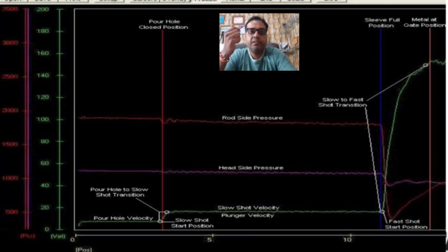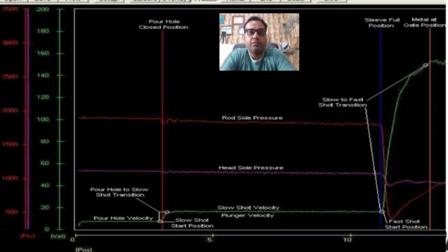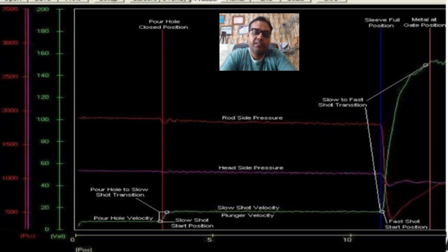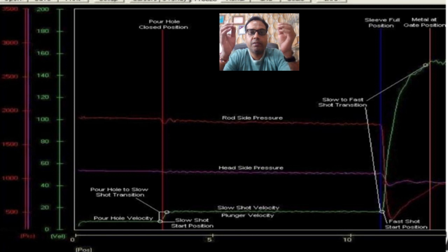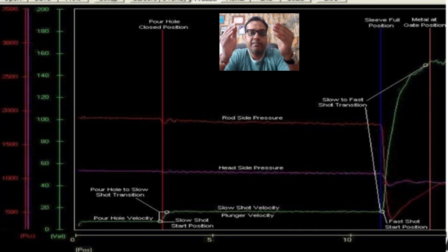Another process parameter is slow shot start position. The slow shot start position is the position where the slow shot velocity is initiated. This setting should be equal to or slightly before the pour hole close position. The slow shot may be set to start before pour hole close because of the hydraulic and electronic delay in initiating the slow shot speed. The means to control this position accurately is to have accurate closed-loop measurement of position via the PLC. When the desired start position is achieved, the PLC should trigger the slow shot to begin. Please note that when using PLC position-based shot control, the normal PLC scan should be interrupted so that timely control of the position-based output may be completed; however, this interruption should not be higher in priority than the safety functions of the die casting machine.